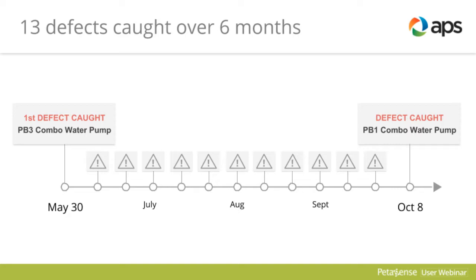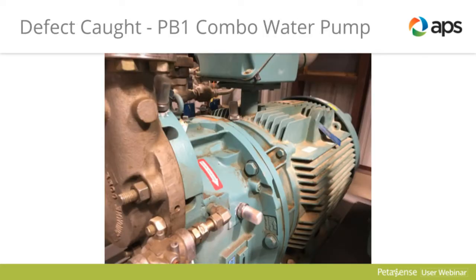Since we did our initial installation, I've had 13 major defects that were caught. The last defect we had was on power block 1, the combo water pump. On September 24th, the plant had asked me to come out to check a different pump and motor that they were going to install. While I was at the plant, I noticed that the combo water pump in power block 1 was cavitating, and that the suction pressure of the pumps was fluctuating. The discharge control valve was also continually exhausting air, and I reported those anomalies to the plant.